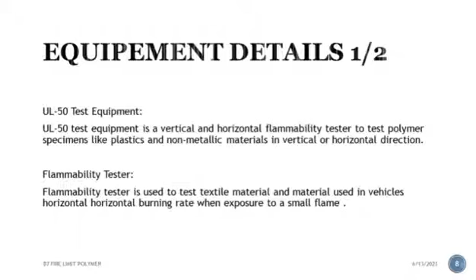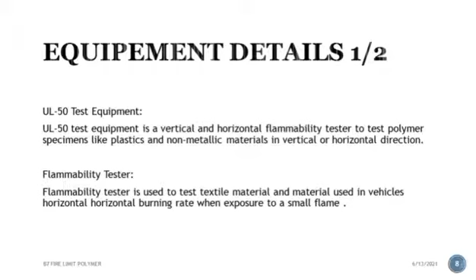First of all, what is the purpose of the UL50 test? It is a vertical and horizontal flammability tester, used to test polymer specimens like plastics and non-metallic materials in both vertical and horizontal directions. Now, what is a flammability tester? It is used to test textile materials and materials used in vehicles for horizontal burning rate when exposed to a small flame. The horizontal burning test evaluates the burning rate of the specimen in millimeters per minute, taking into account its thickness.